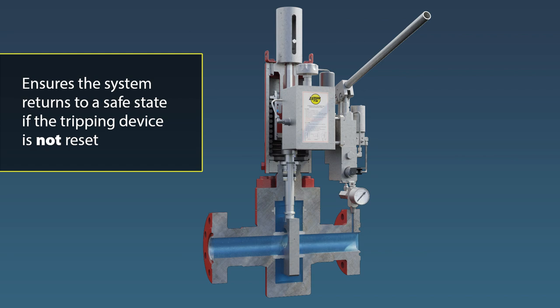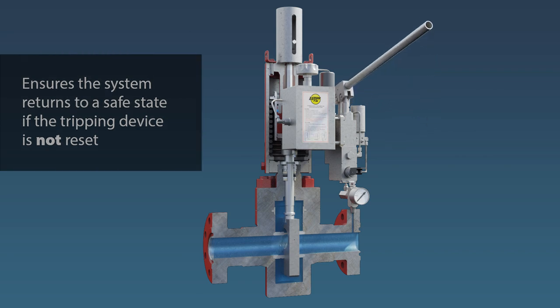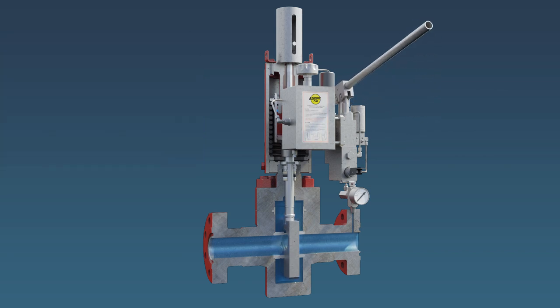For added safety, when the TRIP devices are back in range and with the manual override valve reset and the SSV pumped fully open, the MOV toggle automatically moves from the override position to the run or auto position.